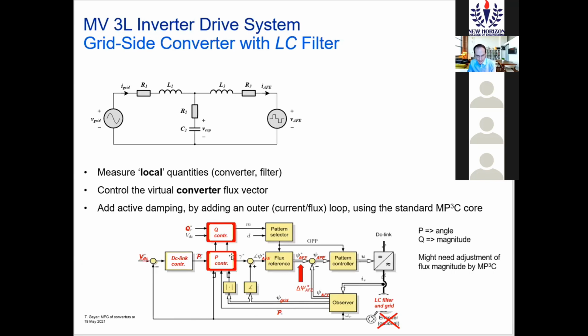And the active power tells you what is the angle between the grid flux and your virtual converter flux. So this one here works with virtual fluxes. And then you use the same principle, plus maybe some active damping loop, where we inject here this delta flux in the active front end to add damping for this LCL structure.